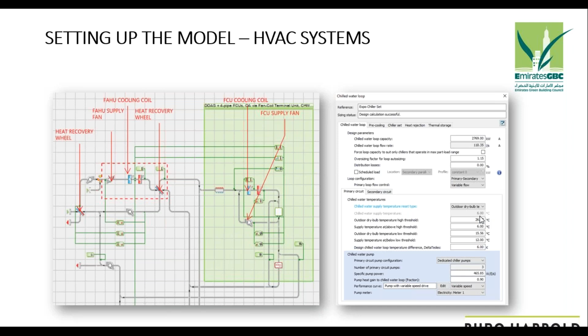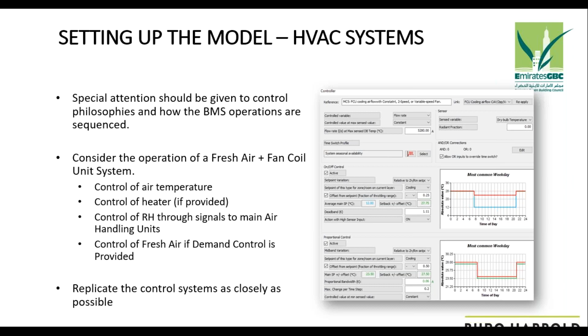Then you have to set up the control systems as well, and you want to inform the control system. For example, for each space, if you had a fan coil unit, you would want to control the air temperature, control the heater, control the room humidity through control of the air handling units, and control any fresh air VAV boxes if you have demand control ventilation for your space. You need to define each of these controls for each space. You want to replicate the control systems as closely as possible and mimic the actual BMS design wherever you can. If you don't have the controller, you can ignore it.